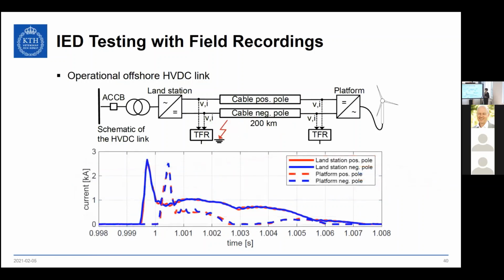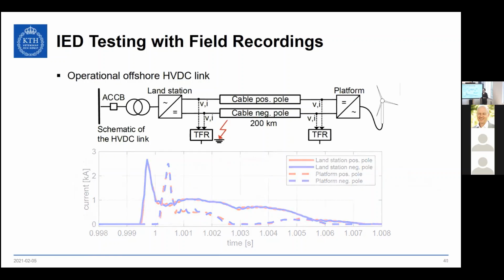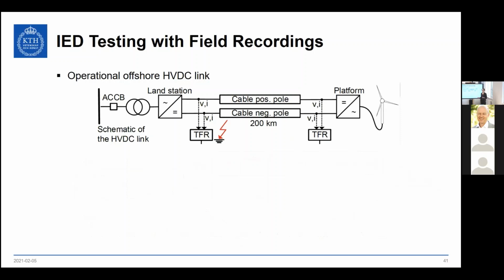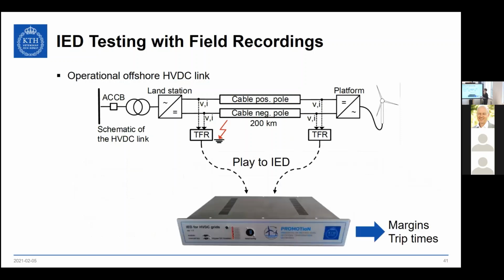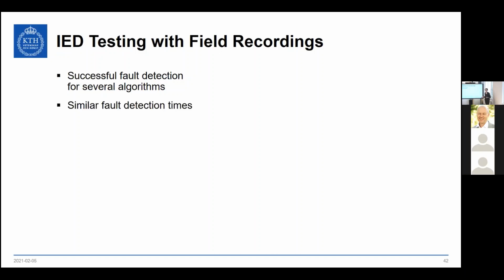These are the current measurements, going up to 2.5 kiloamps. What I did is take these measurements, feed them to the IED, and observe the margins and trip times. In short, the device could successfully detect this fault with several algorithms and similar fault detection times, but with different margins depending on the configuration.